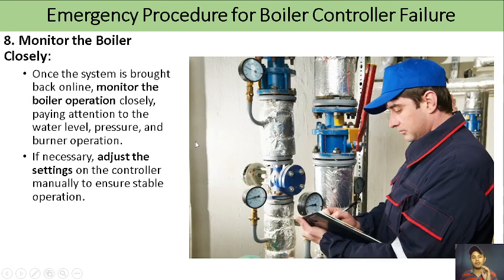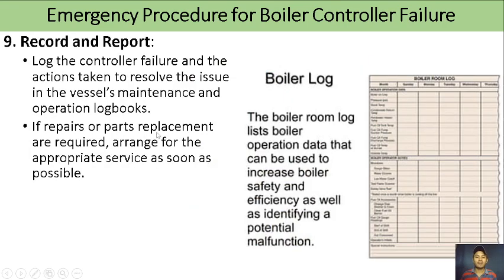And then monitor the boiler closely if you are starting it in manual, or if the controller is now operational, still monitor the boiler closely. Once the system is brought back online, monitor the boiler operation closely, paying attention to the water level, pressure, and burner operation. If necessary, adjust the settings on the controller manually to ensure stable operation. And then record and report the problem, log the controller failure and the actions taken to resolve the issue in the vessel's maintenance and operation logbooks. If repairs or parts replacements are required, arrange for the appropriate service as soon as possible.